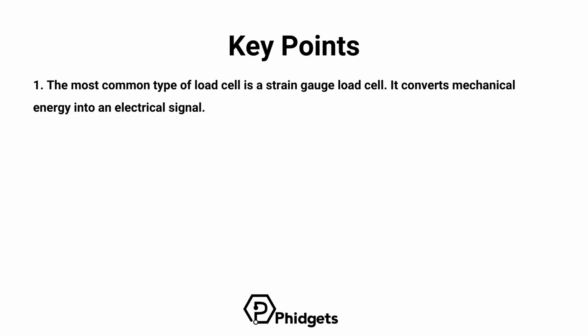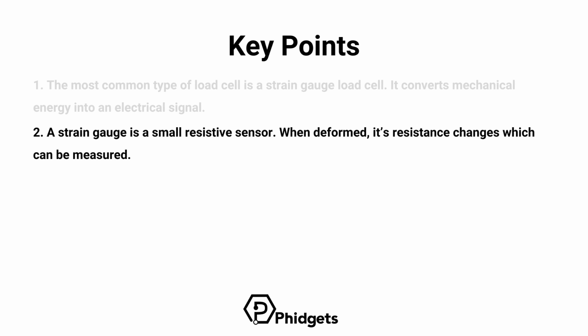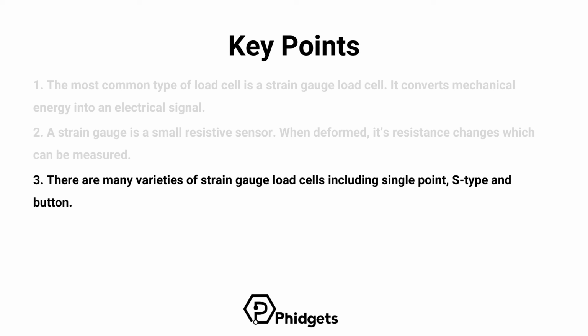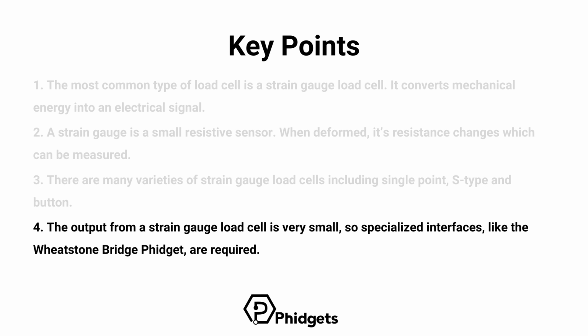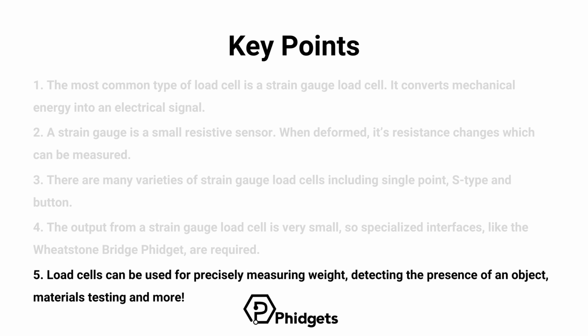Here are some key points that we've learned. The most common type of load cell is a strain gauge load cell. It converts mechanical energy into an electrical signal. A strain gauge is a small resistive sensor. When deformed, its resistance changes, which can be measured. There are many varieties of strain gauge load cells, including single point, S-type, and button. The output from a strain gauge load cell is very small, so specialized interfaces, like the Wheatstone Bridge Phidget, are required. Load cells can be used for precisely measuring weight, detecting the presence of an object, materials testing, and more.